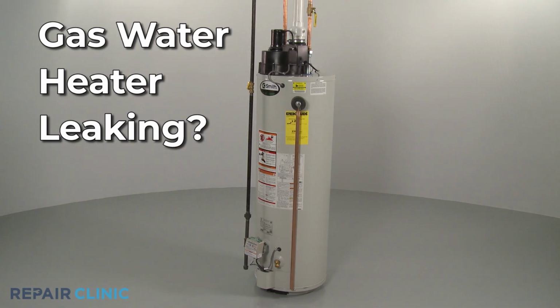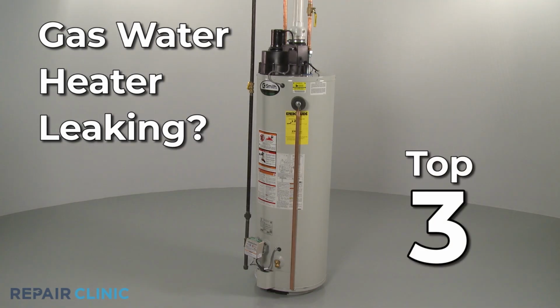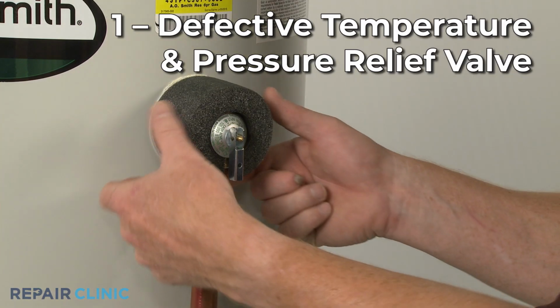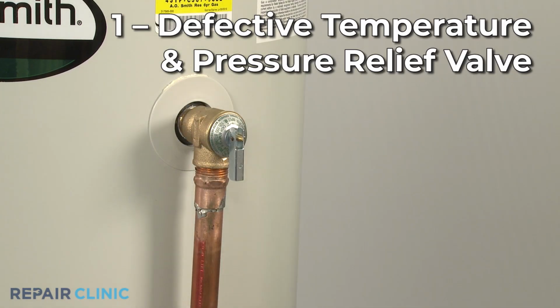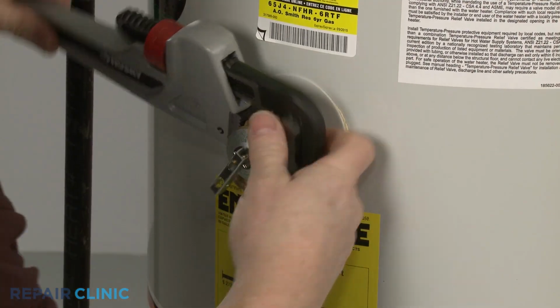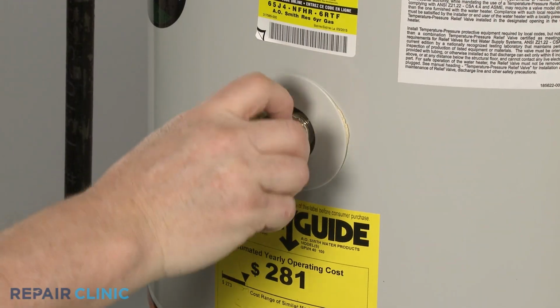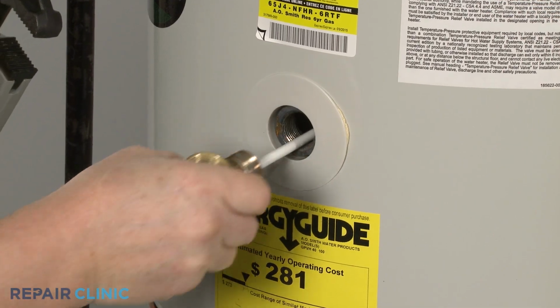If your gas water heater is leaking, here are the top 3 most probable causes. The temperature and pressure relief valve is designed to open if the temperature or pressure exceeds the proper level indicated on the valve itself. A defective valve may release water regardless of the temperature level and will need to be replaced with a new one.